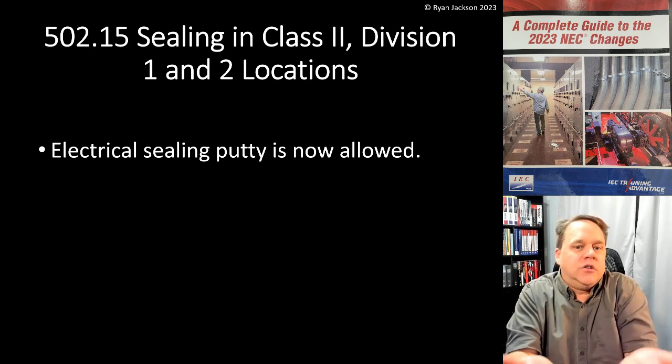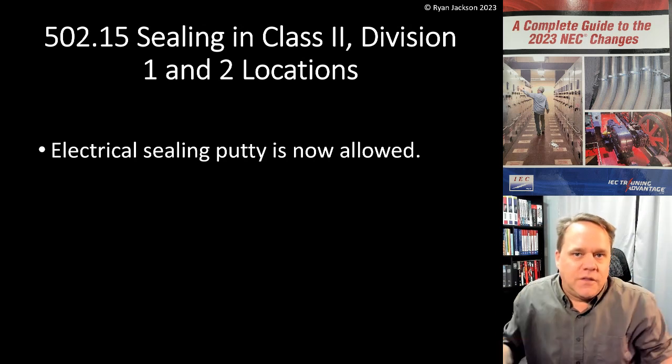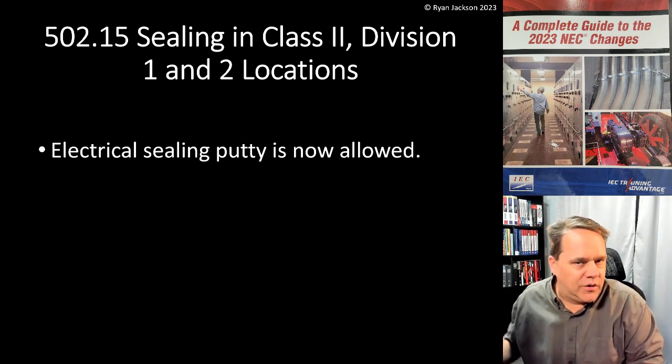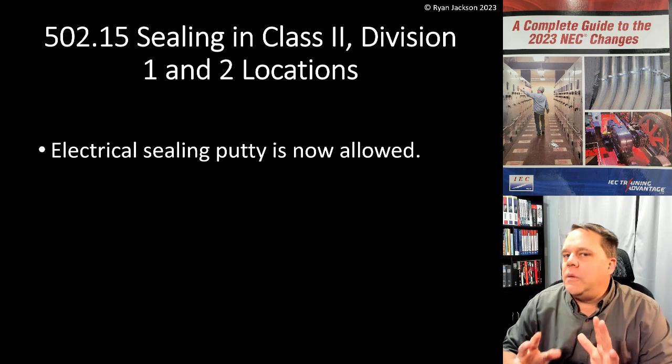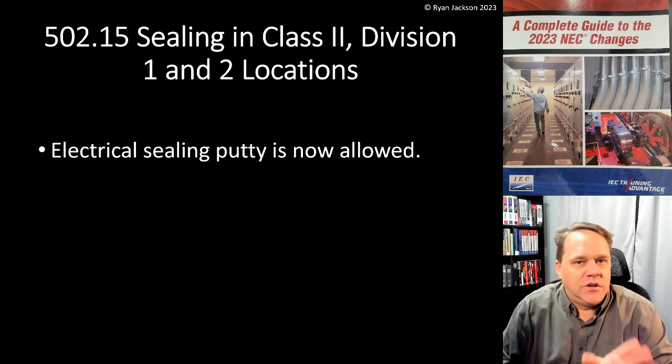You can use electrical sealing putty. You grab a handful of putty and stuff it in the pipe — that's it. That's how you seal a raceway in a Class II location. A lot of people get really carried away with how they seal things in a Class II location.